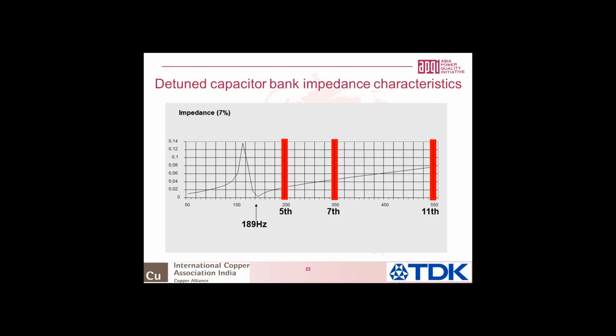For example, if you're choosing a capacitor which is going to be connected to the 440 volt system, but you're using a series reactor, the voltage across the capacitor would be more because of the series inductive drop. That means we need a capacitor with a higher voltage rating, considering not only the harmonic voltage but also the fundamental voltage. And if you're choosing a capacitor to be used with a 5.67% reactor, then the capacitor should have a higher current carrying capability, not just 1.3 or 1.5, maybe up to even 1.8 times the rated current, because you are now going to do a partial filtering.